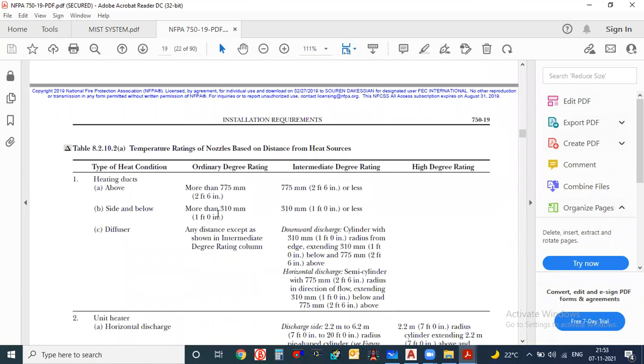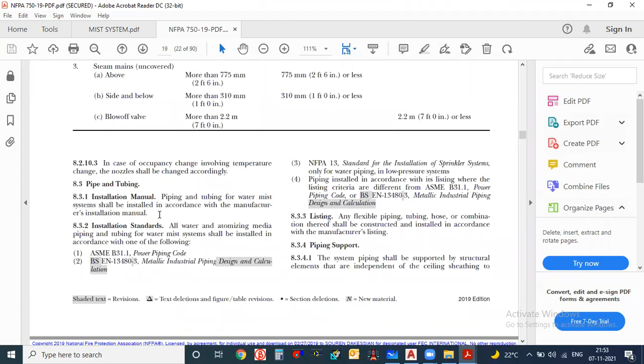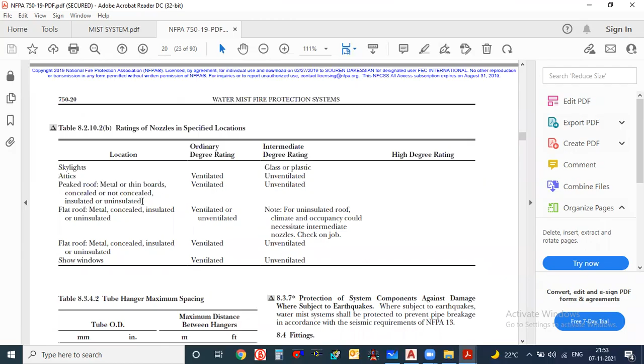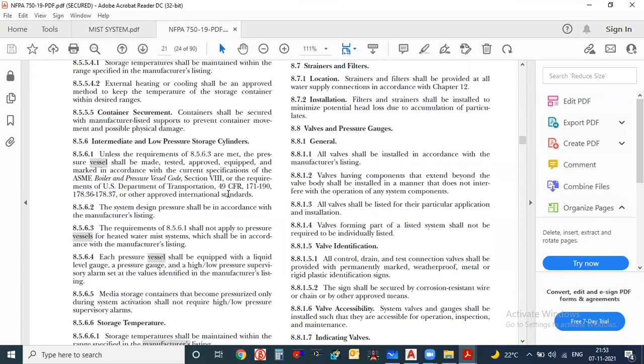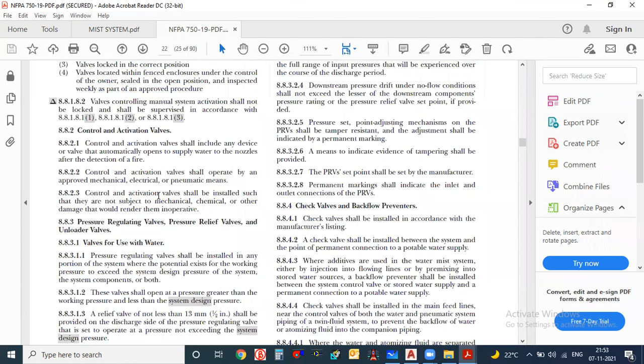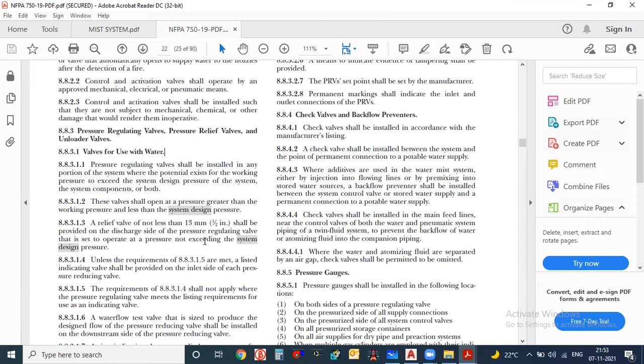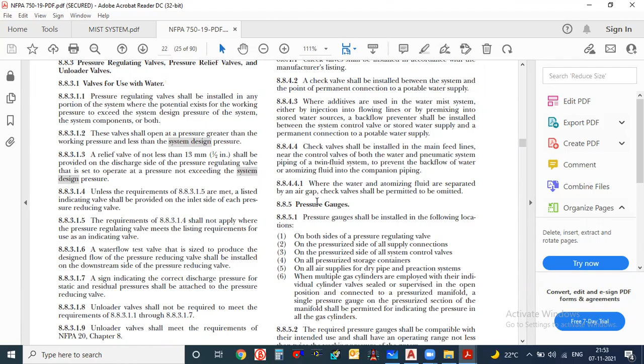Temperature rating of nozzle and so on, okay, these things are not actually required. Some things are given here. Hanger maximum spacing and all, okay, spacings are given. You can leave this. Valves and pressure gauges, something about the valves and all is given here. And check valve, backflow preventer, pressure regulating valve. Again, here they have given the pressure regulating valve, and you have to understand where you are installing PRVs: if the pressure is going high, there we have to install this pressure regulating valve. So obviously with the help of Elite software, you can easily design. You have to follow the same procedure, just change the pressure values, and based on that you have to design. And here they have given the locations where you can install the pressure gauges. Like that, some things are given.